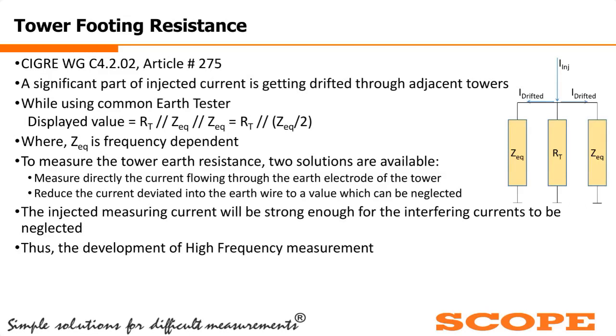Now, while using our common earth tester, we will get the earth resistance value in which the influence of other towers, the other towers which are grounded at different locations, also comes into the picture. Due to that, we get our tower resistance along with the Z equivalent. This Z equivalent consists of the effect of the adjacent towers, so this impedance will also get calculated with the help of the common earth tester. That's why, to reduce the effect of Z equivalent in the measurement, we use the high frequency earth resistance meter.